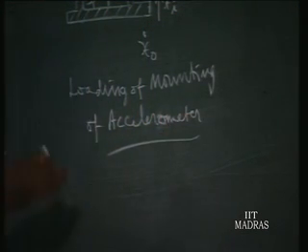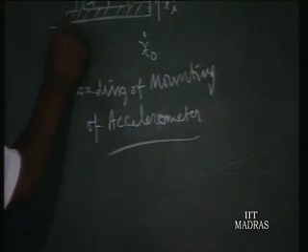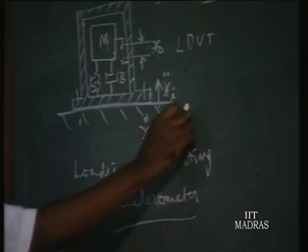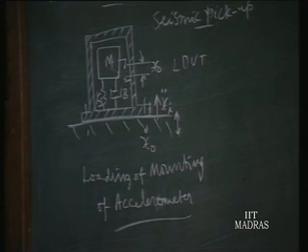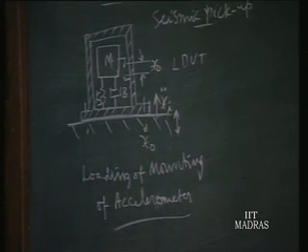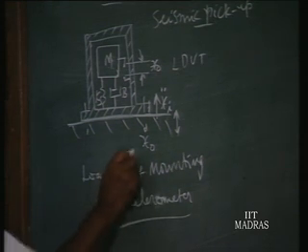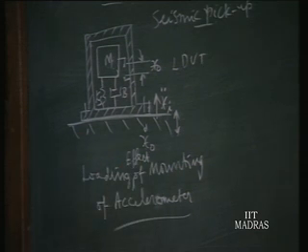What is the loading effect? When we mount an instrument over a vibrating body — we bolt the accelerometer onto the vibrating body which is vibrating up and down — whether the amplitude or the magnitude of acceleration will get affected because we are bringing extra mass over the vibrating body. So the acceleration may get affected; that is called the loading effect of the accelerometer.